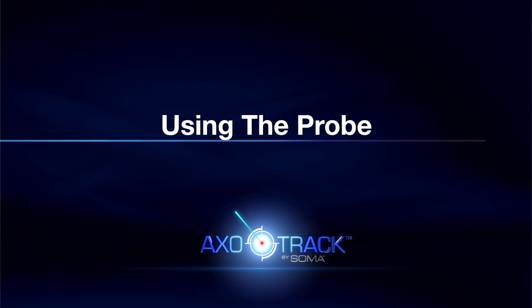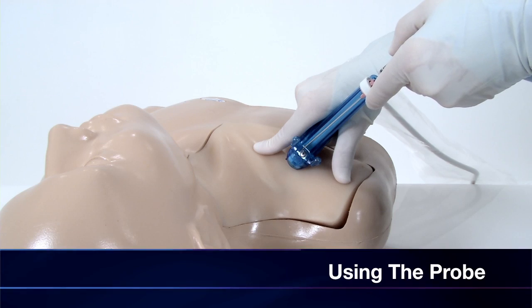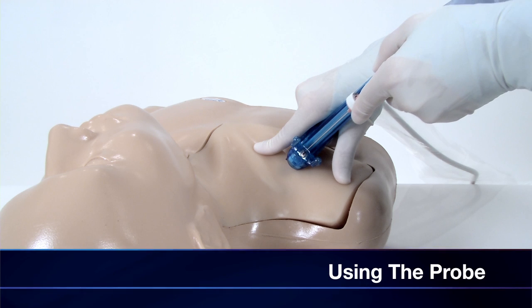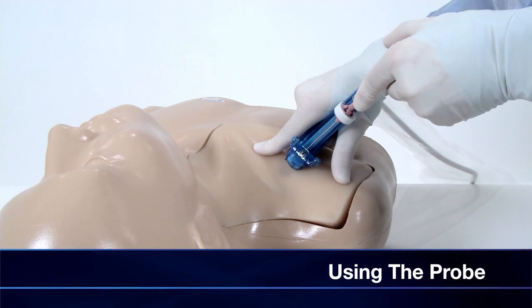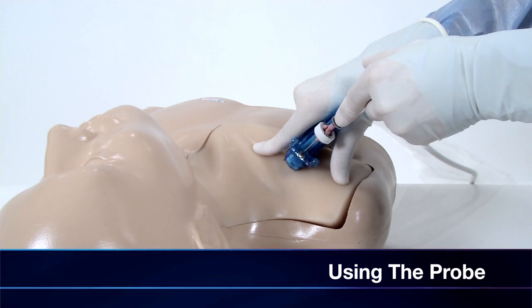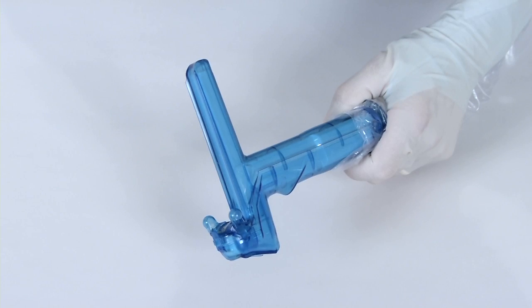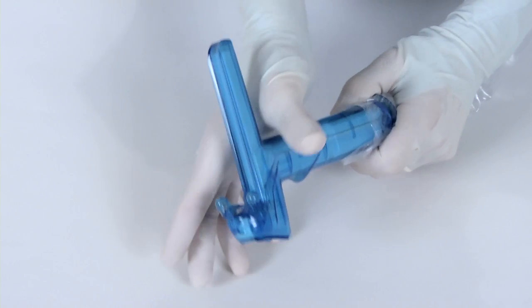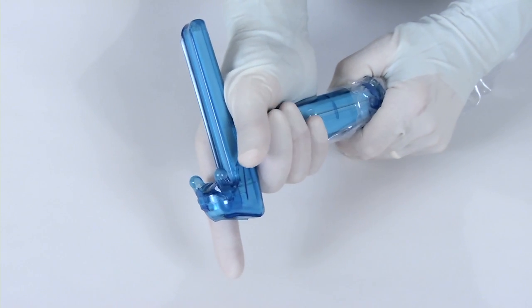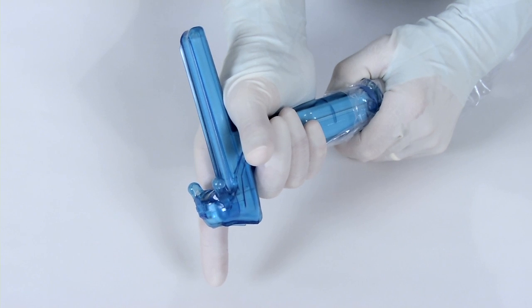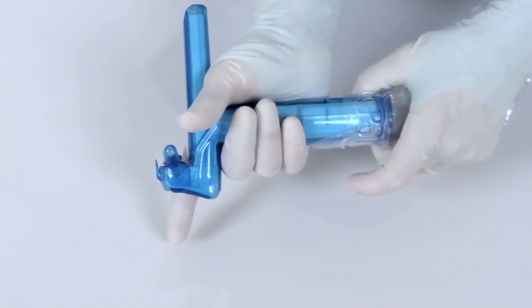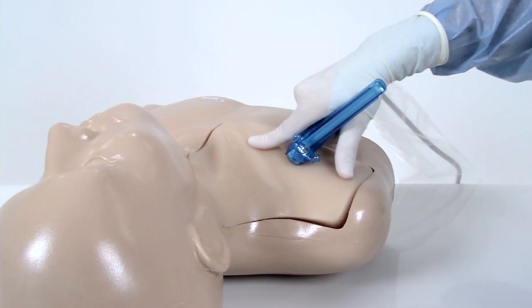The AxoTrack equipped probe with probe shield has an ergonomic design that allows it to be held securely, facilitating accurate needle guidance. The probe can be held in either hand, with the vertical post pressed into the dorsal first web space. The finger grip on the probe handle is then gripped with the middle finger, leaving the forefinger and thumb to act as stabilizers on the surface of the body.